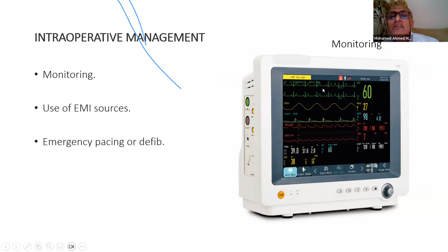Regarding the electromagnetic interference, if the surgeon will use cautery, we will advise the surgeon to use bipolar if possible, and to decrease the dependence on the monopolar. But as we know, the most common mode of the diathermy used during surgery is a monopolar, either cutting or coagulation mode.